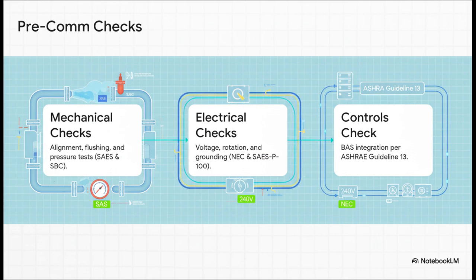Okay, before you even think about starting this thing up, you've got to run your pre-commissioning checks. Think of it like a final pre-flight inspection. Mechanically, you're making sure pipes are clean and can take the pressure. Electrically, you're checking that the power is right and the motors spin the correct way. And of course, you're making sure the brains of the operation, the building automation system, is actually talking to everything.